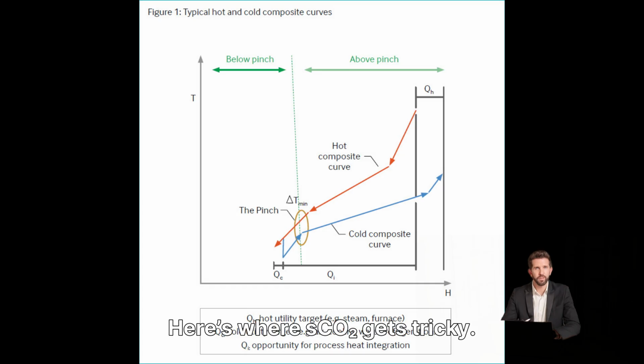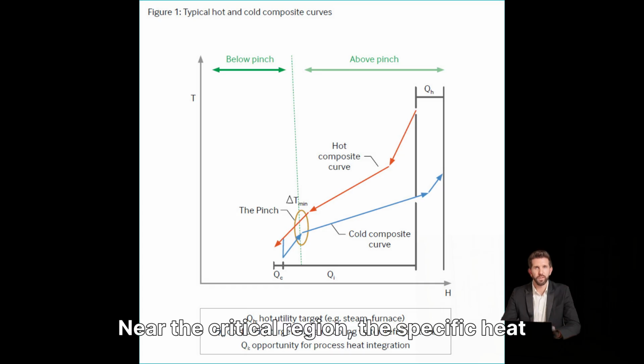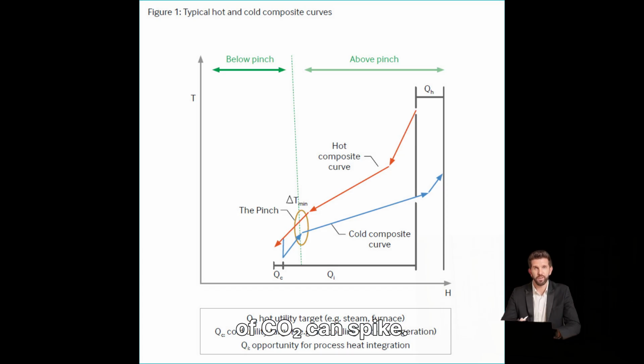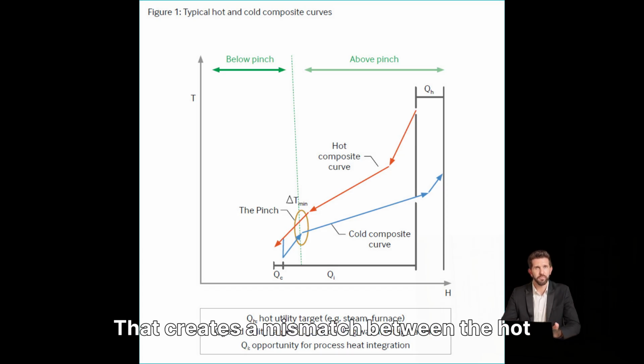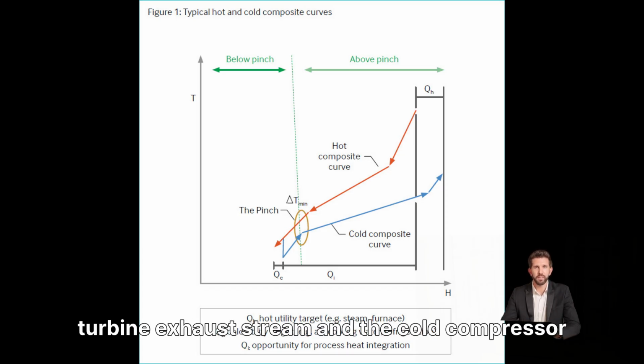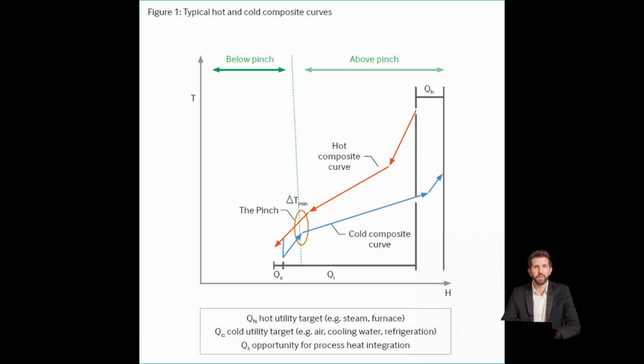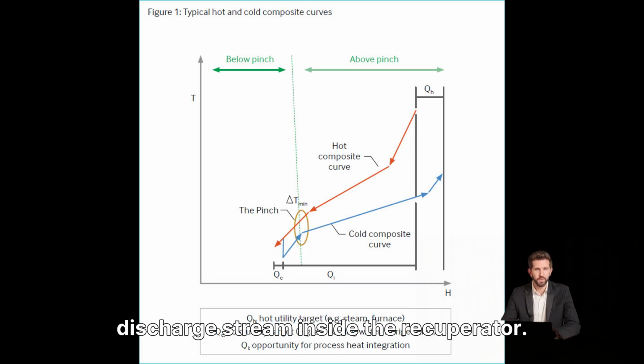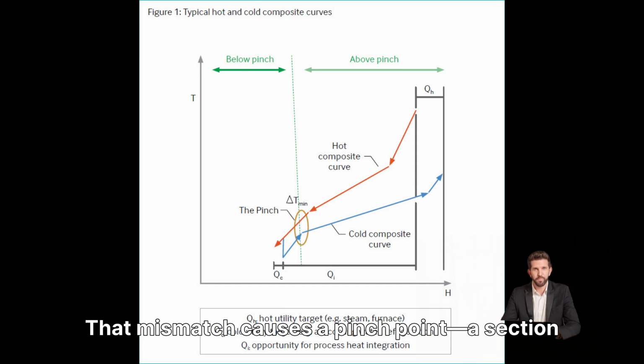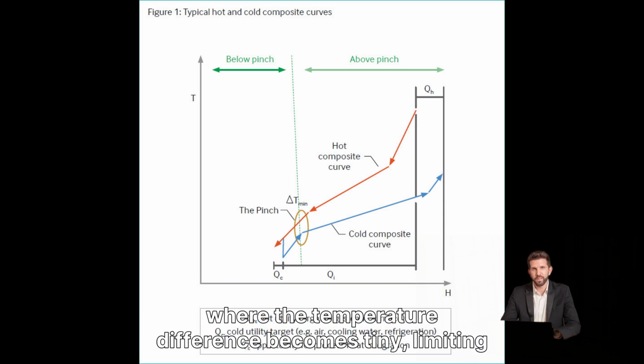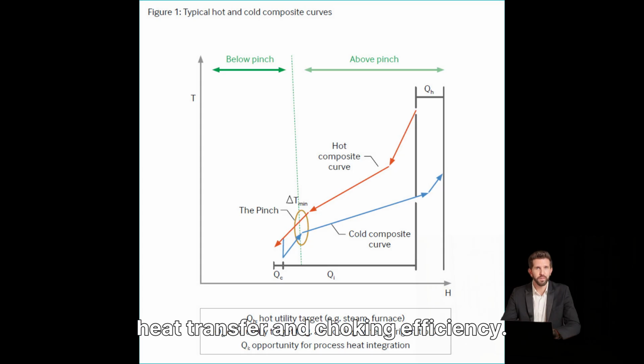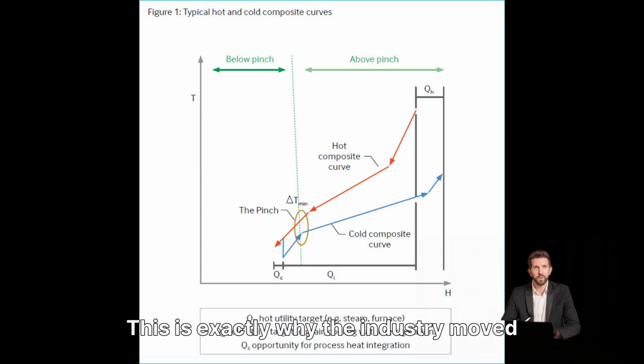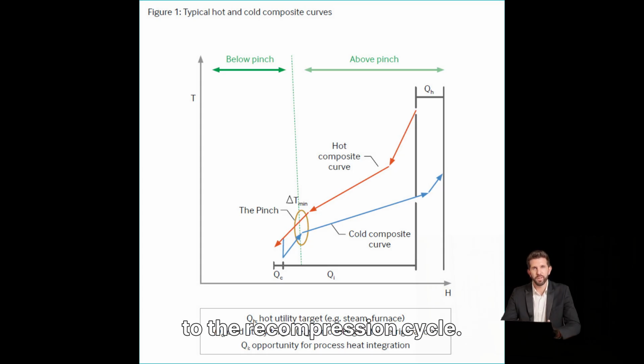Here's where SCO2 gets tricky. Near the critical region, the specific heat of CO2 can spike. That creates a mismatch between the hot turbine exhaust stream and the cold compressor discharge stream inside the recuperator. That mismatch causes a pinch point, a section where the temperature difference becomes tiny, limiting heat transfer and choking efficiency. This is exactly why the industry moved to the recompression cycle.